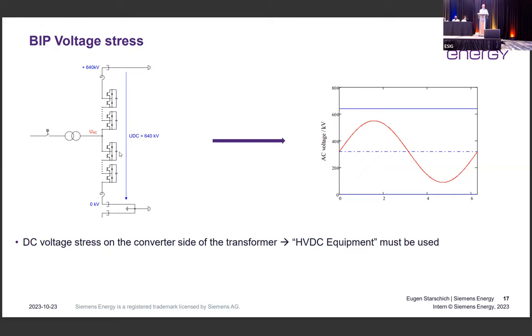From the converter point of view, it's no different. The converter is still producing 640 kV. You're going to have the same converter for the symmetrical monopole or for this bipolar system. But all the other DC equipment, like the DC transmission cable, sealing ends and reactors, is designed for this higher voltage. And on the AC equipment, you will get a certain DC voltage offset. This means that all the equipment installed here has to handle the AC voltage stress plus the DC voltage stress.